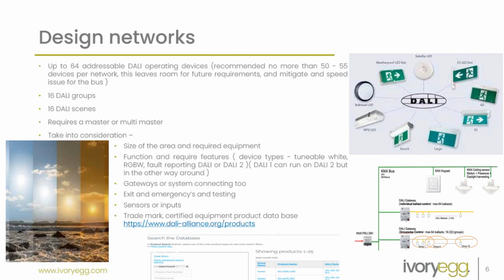If you're not sure if a device is Dali certified, there are websites where you can go and see the trademark has been issued to the product, and this certifies the product in the database to ensure that you have got a certified Dali brand. Lots of overseas and particularly Asian manufacturers produce Dali products, and they say they're Dali. They haven't been tested or certified, and sometimes you waste lots and lots of time with illegitimate products.